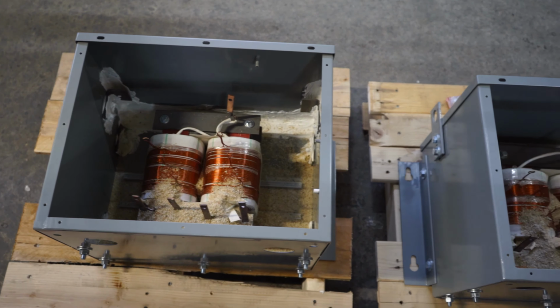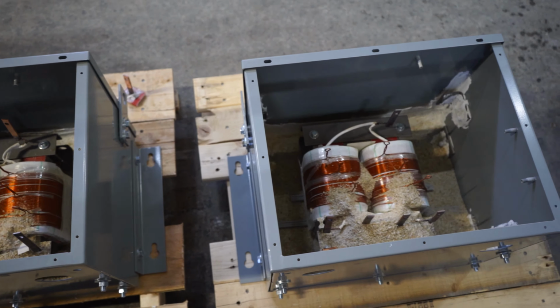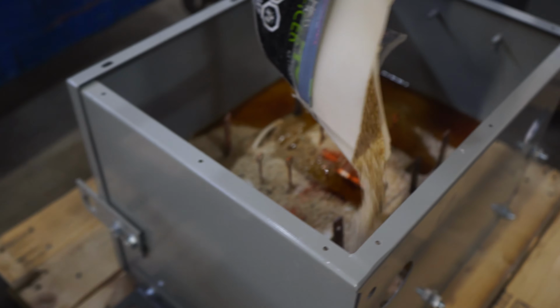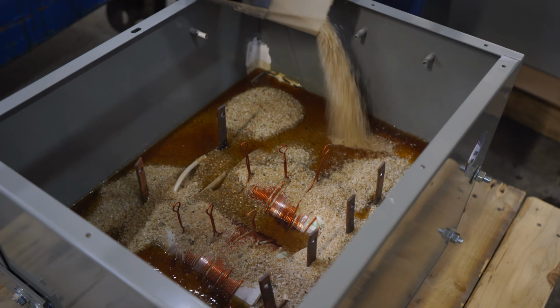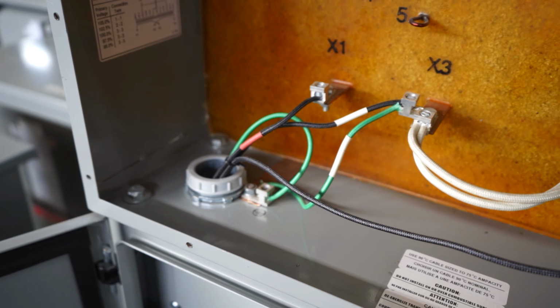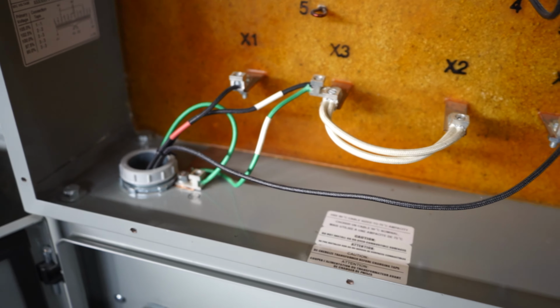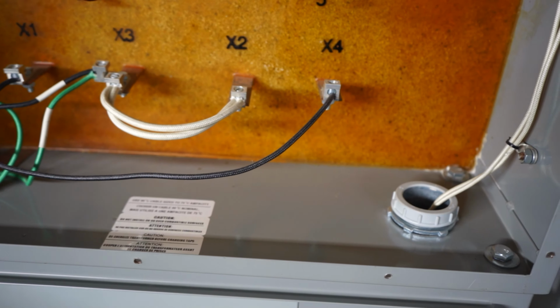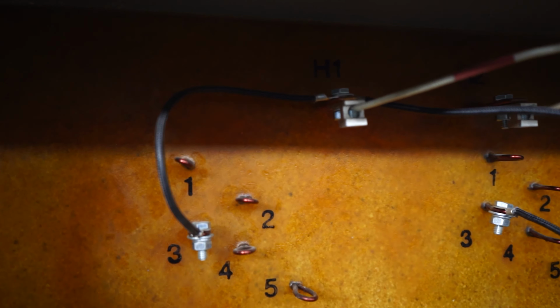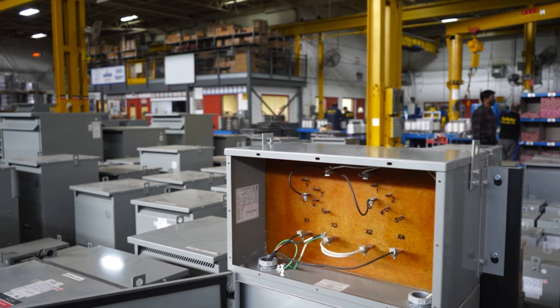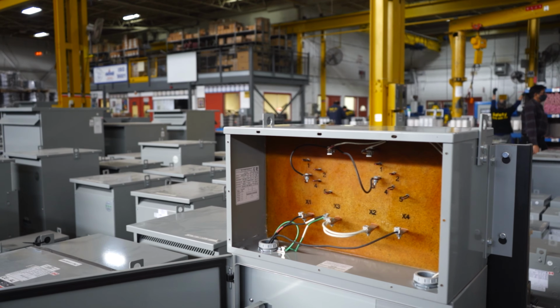The complete core and windings of the transformer are encapsulated in a silica sand and polyester resin mixture with only the leads and taps brought out. This construction makes the transformer impervious to moisture, dust, and contaminants in the air, in addition to providing the maximum bracing and toughness to handle transportation and installation in demanding and harsh environments. This makes for what is essentially a maintenance-free transformer.